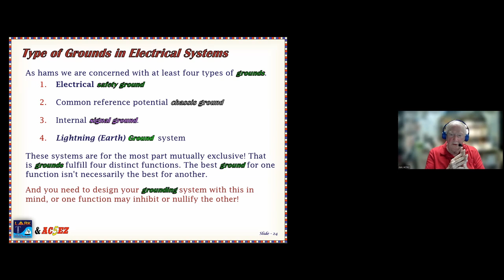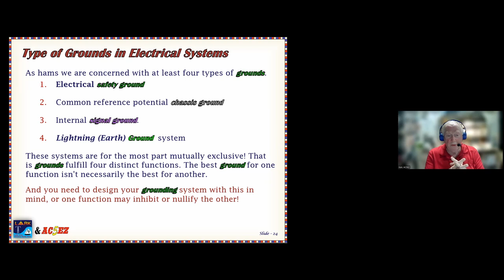And you need to design whatever you're doing to make sure that you don't nullify one, like a signal ground. If you say, well, I'm going to just take that signal ground to earth ground, you might in fact totally disconnect whatever the circuit was supposed to be doing. And you might even damage your equipment. So you need to make sure that your grounding system takes into account all of these different grounds and you don't try to nullify one of them.